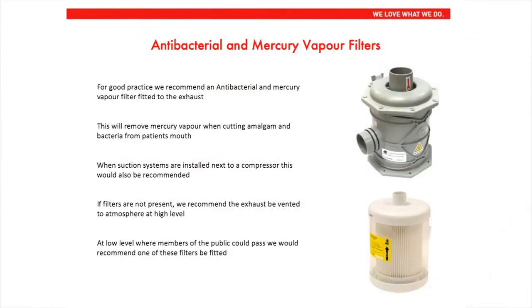Antibacterial and mercury vapour filters. For good practice, we recommend an antibacterial and mercury vapour filter fitted to the air exhausts. This will remove mercury vapour when cutting amalgam and bacteria from the patient's mouth. When suction systems are installed next to a compressor, this would also be recommended.